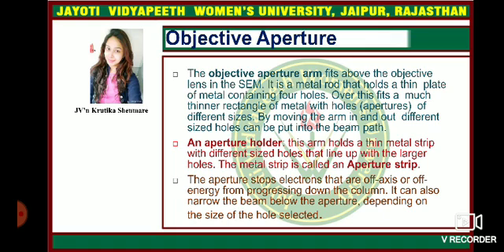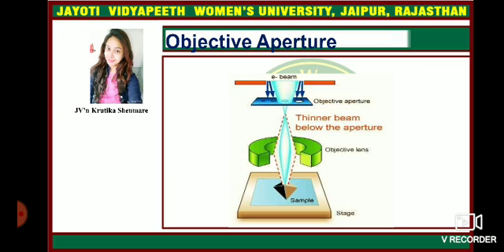The aperture stops electrons that are off axis and off energy from progressing down the column. It can also narrow the beam below the aperture depending on the size of the hole selected. So this is how the objective aperture looks.